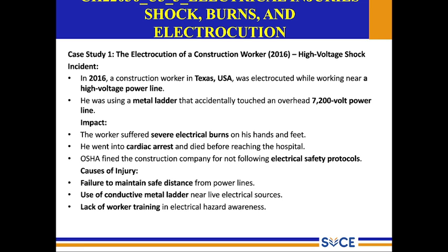First, we'll have case study one: the electrocution of a construction worker, a 2016 high voltage shock incident. The incident happened in 2016 at a construction site. A construction worker in Texas, USA, was electrocuted while working near a high voltage power line. He was using a metal ladder that accidentally touched an overhead 7200 volt power line.